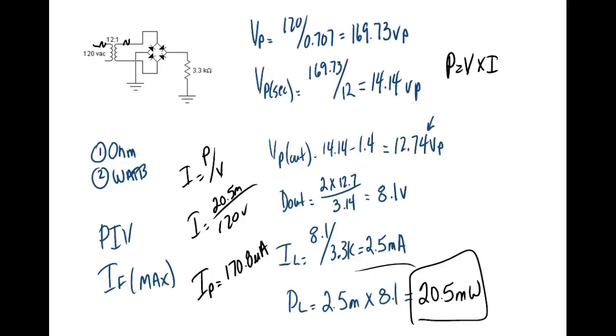So this would be a little tiny transformer, wouldn't be rated at - and of course, that's another thing: you size your transformer to run the load. You're not going to go out and buy a 50 amp transformer to run a 20.5 milliwatt load, right? You'd be spending - you got a transformer here that could charge a golf cart on the secondary side. When we say 20 amps - I shouldn't say that - say a 5 kVA, well that transformer there is a 5 kVA transformer to run that robot, and you see how big that sucker is.